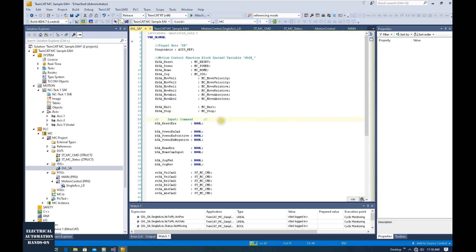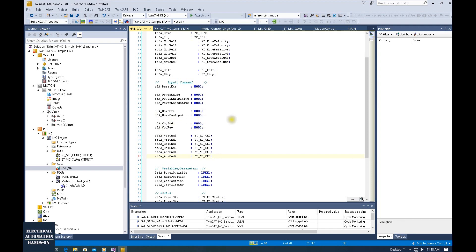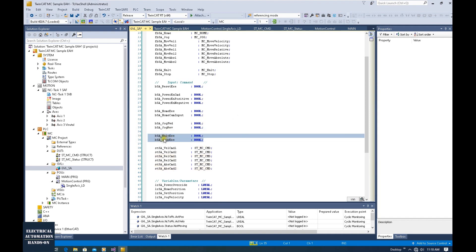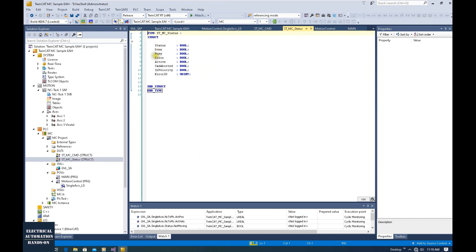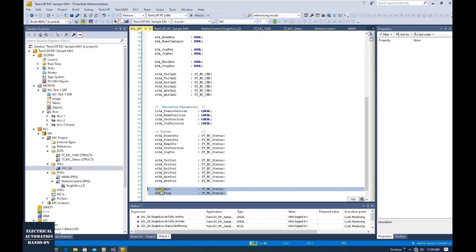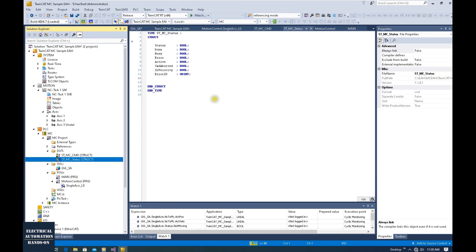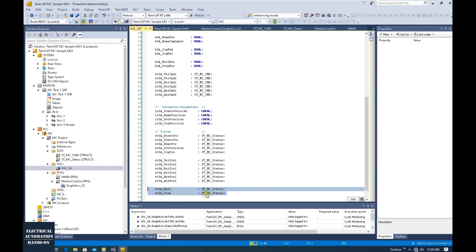For the trigger signal, let's create two boolean signals used to trigger the halt or stop. I declared a Halt_Execute boolean signal and a Stop_Execute boolean signal. And other than this, let's declare some status variables here. This status will be based on the ST_MC_Status structure — a structure I created in a previous video in this playlist. This structure includes status: done, busy, error, active, and error ID. I will declare ST_SA_Halt based on this structure, and ST_SA_Stop based on MC_Status as well.